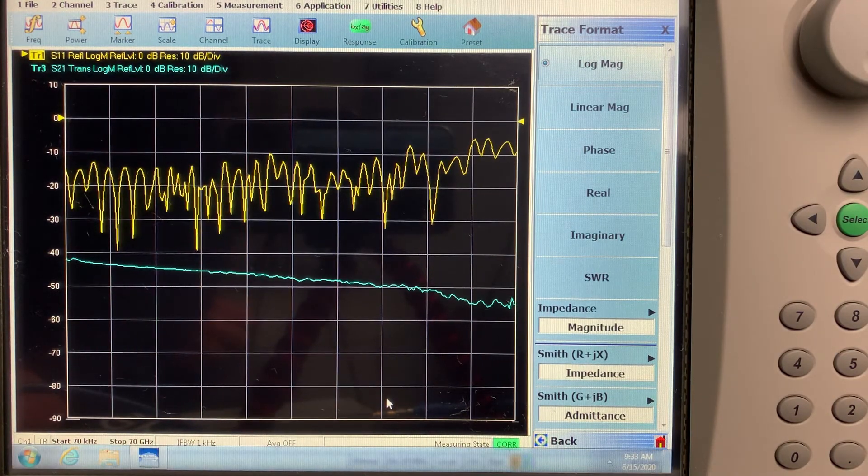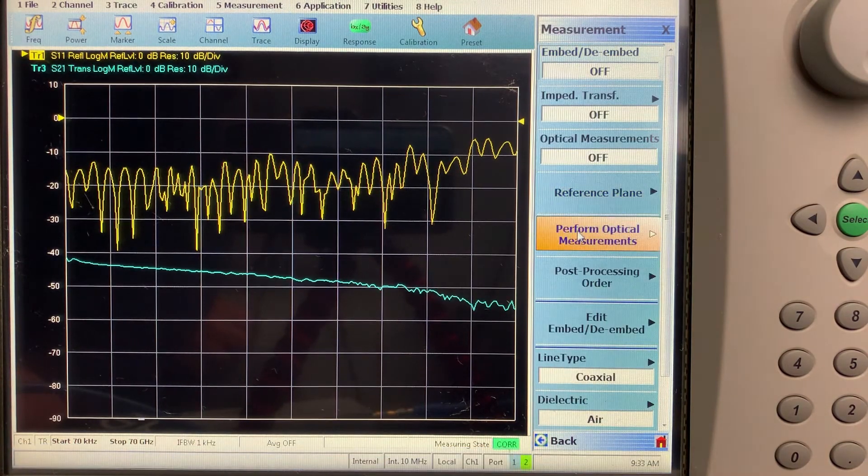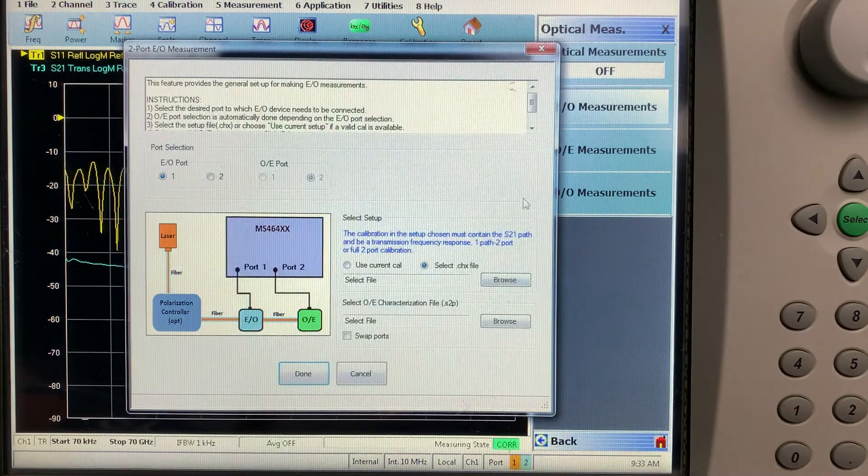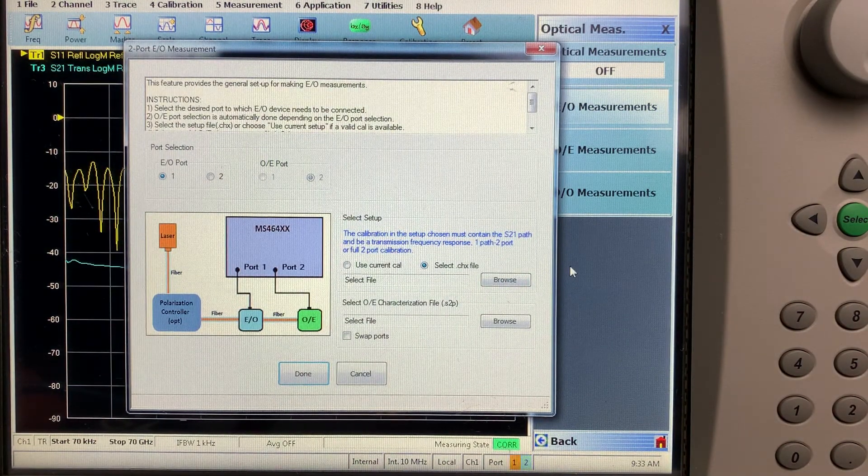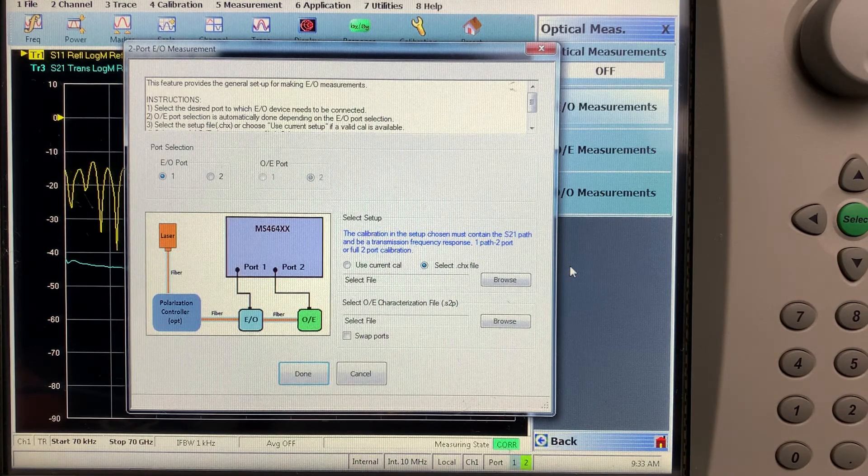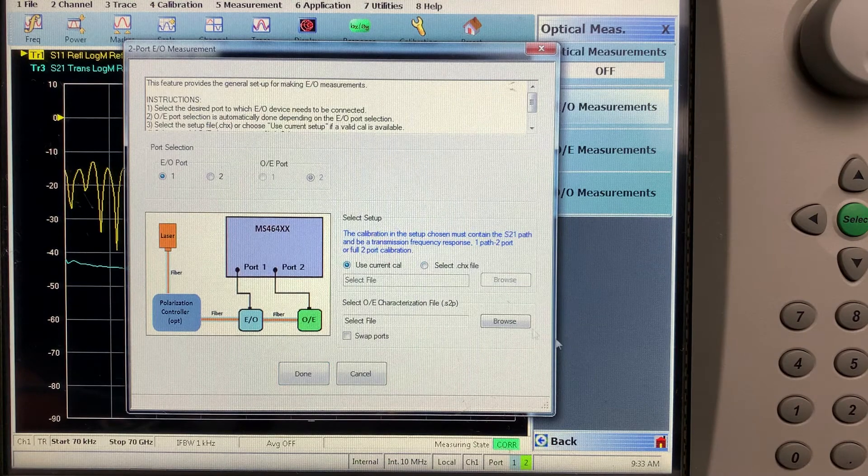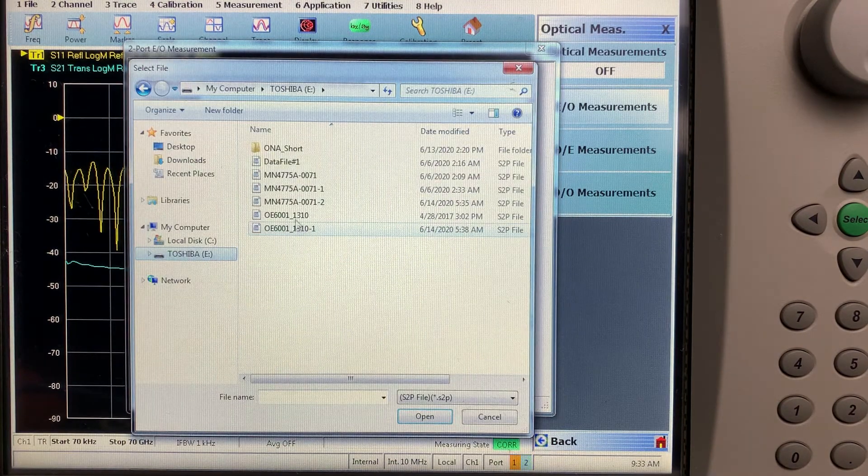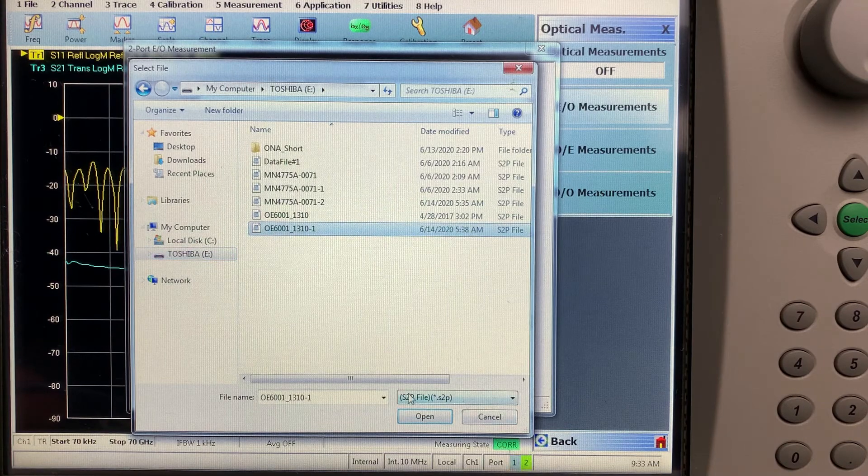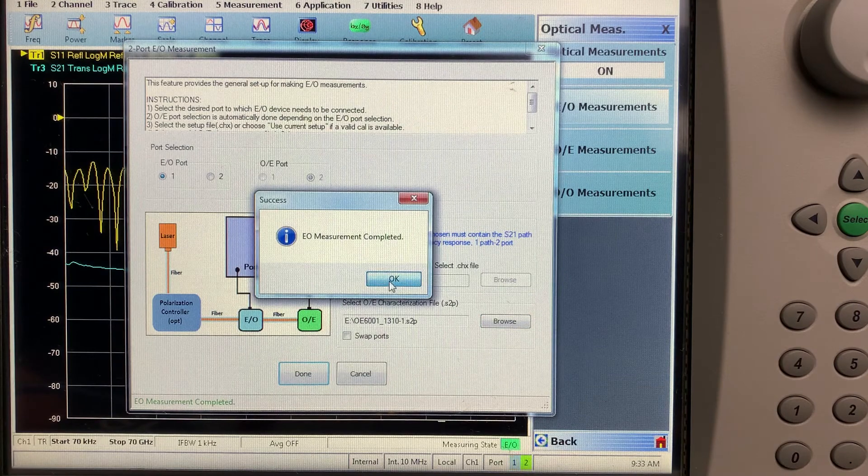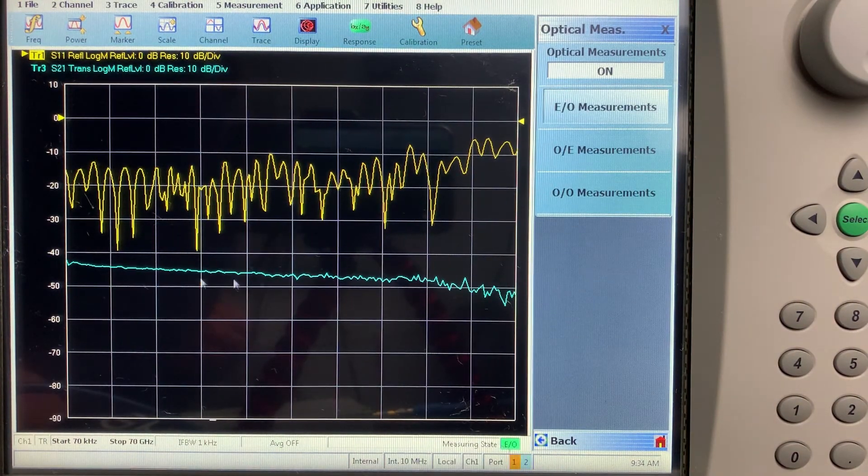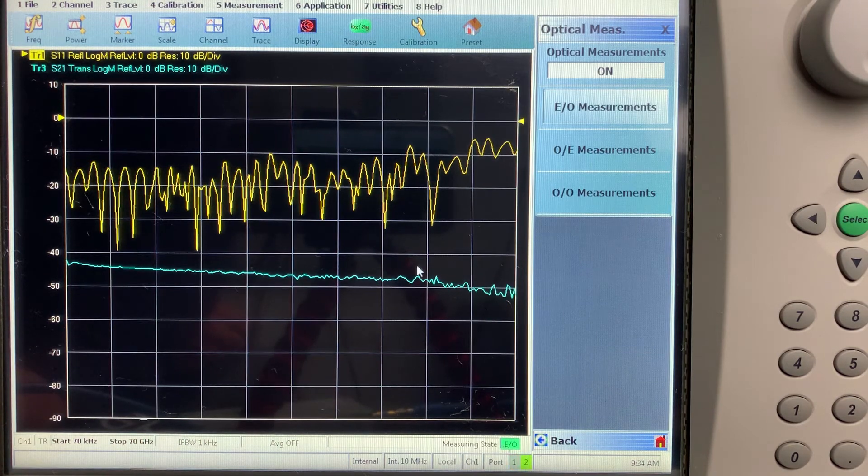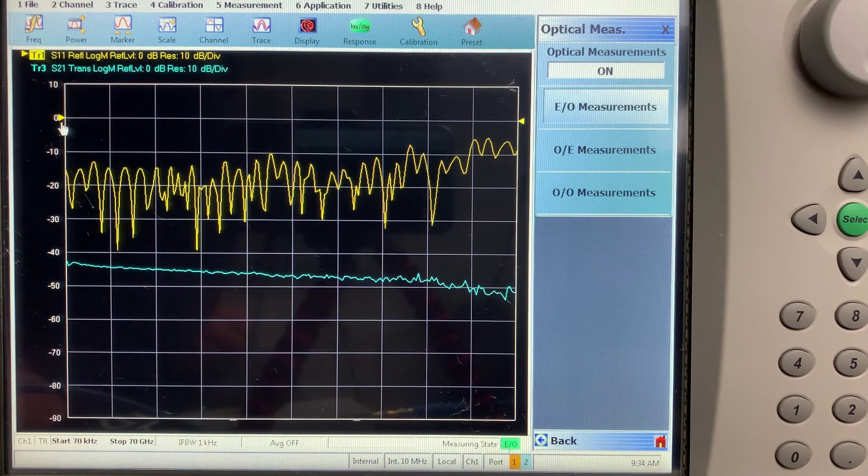So now it's time to do the de-embedding. So we invoke our measurement menu. Perform optical measurements. We're going to do E2O since we already know the characterized data of the MN4765B. We'll de-embed. And what will be left will be the MN4775A S2P data. So we use the current error correction for our S2P file. Press done. And you can see, here's the corrected measurement.